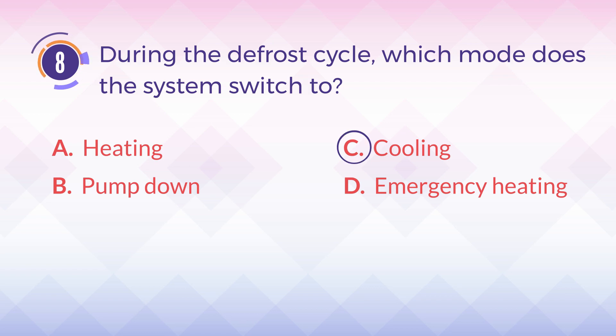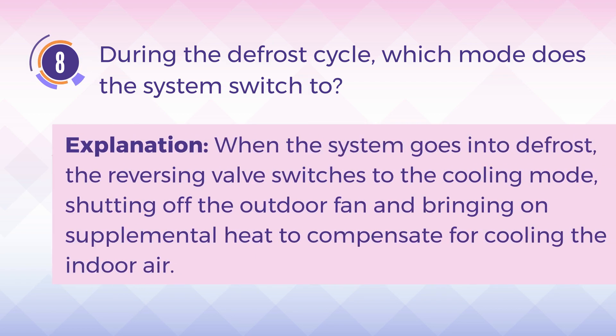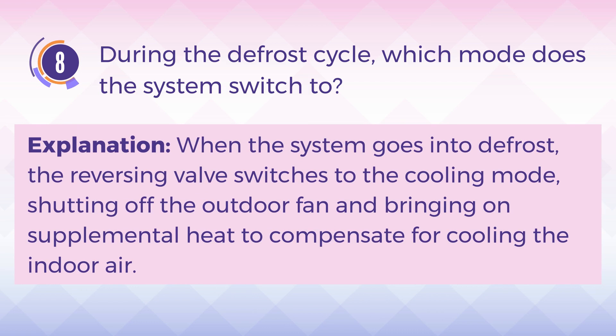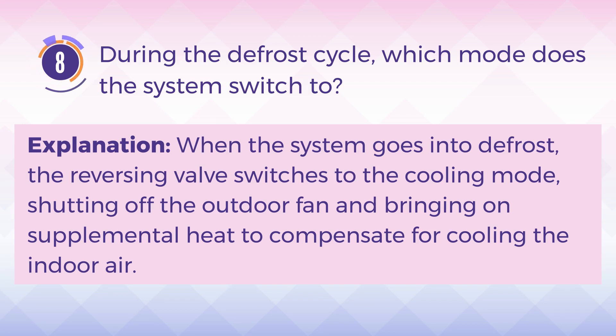The answer is C, cooling. Explanation: When the system goes into defrost, the reversing valve switches to the cooling mode, shutting off the outdoor fan, and bringing on supplemental heat to compensate for cooling the indoor air.